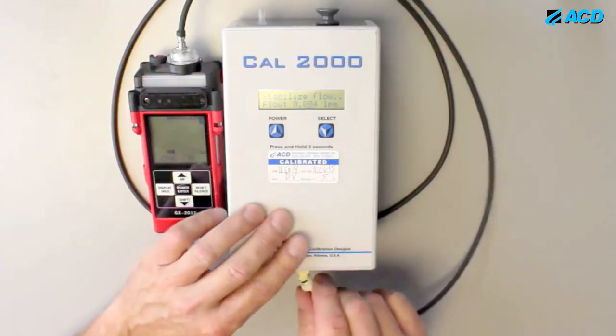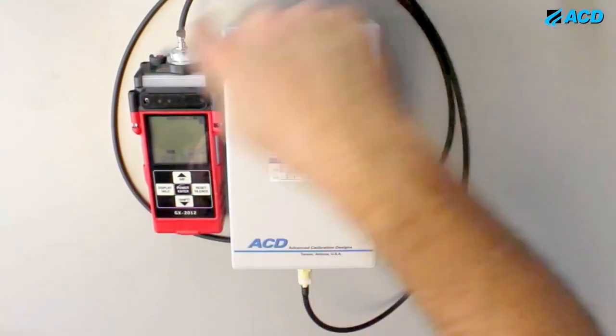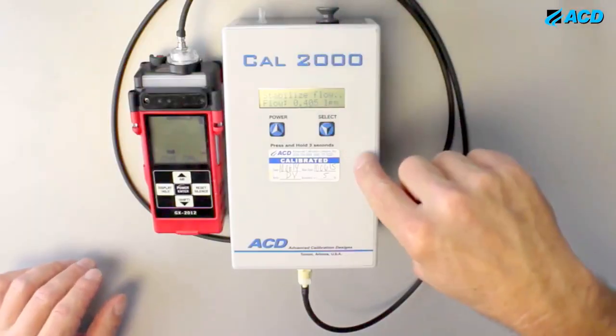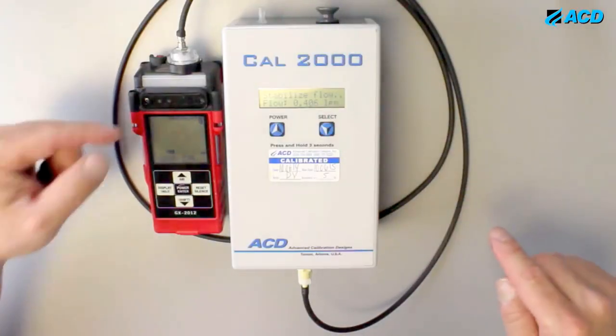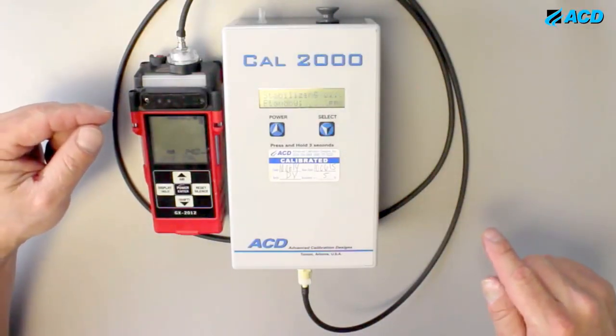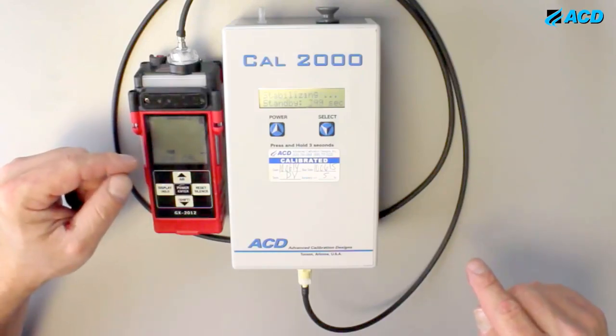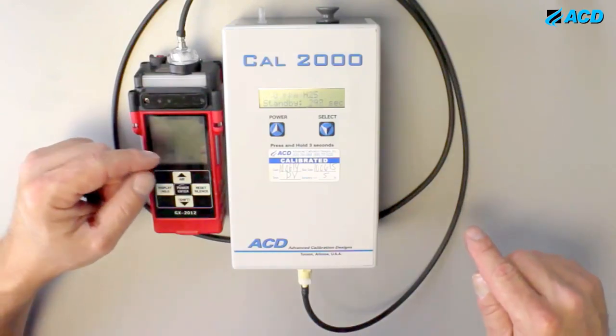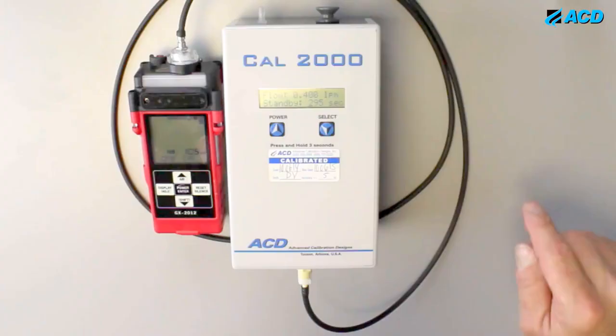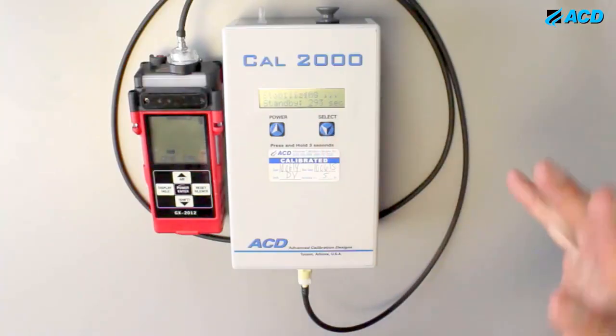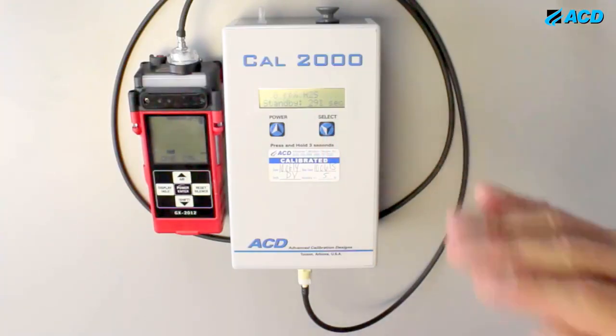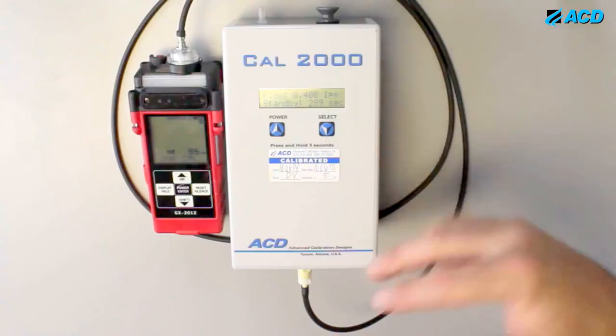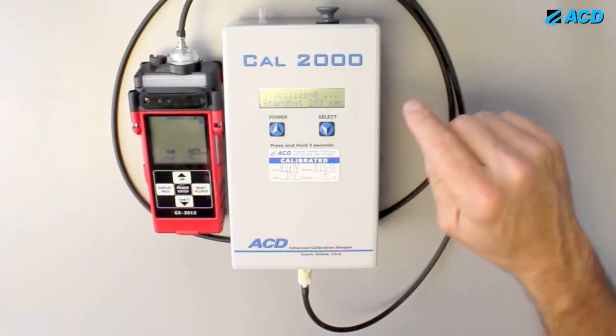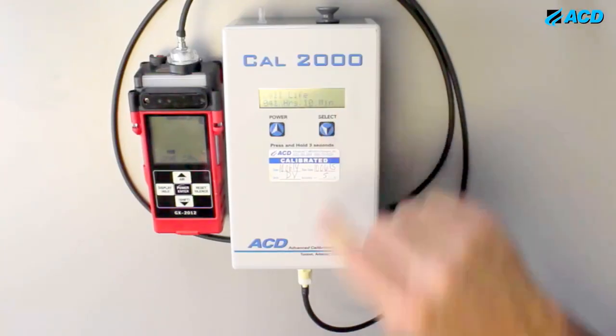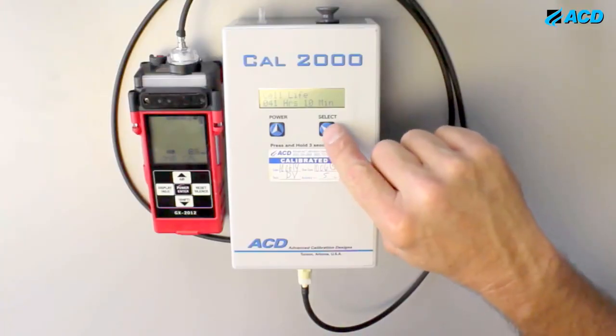So what I'm going to do is hook up this GX 2012 to my Cal 2000, and it is measuring the flow. So it says, okay, I'm pulling in a sample at about 0.4 liters per minute. All right. Now, when you stop the flow, it automatically shuts off the current to the cell, so it doesn't generate gas into a dead space. So the first time you do that, you have to select the concentration you want.